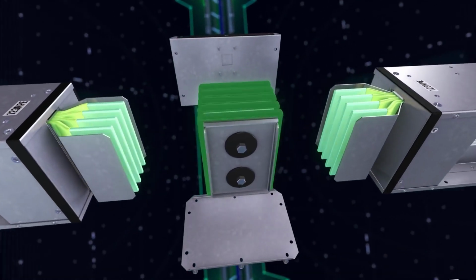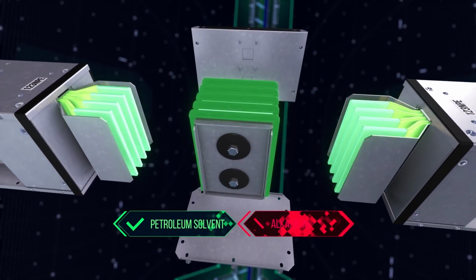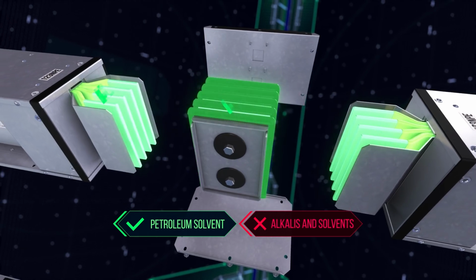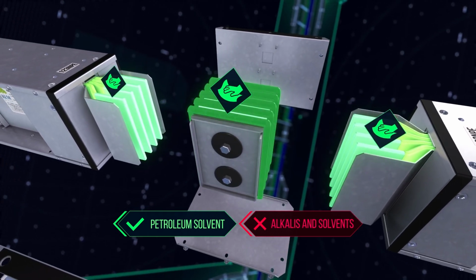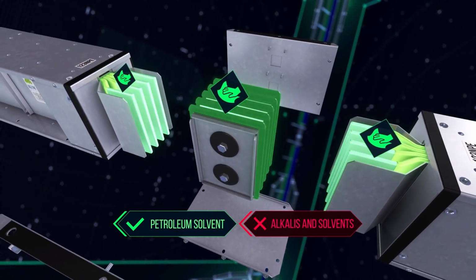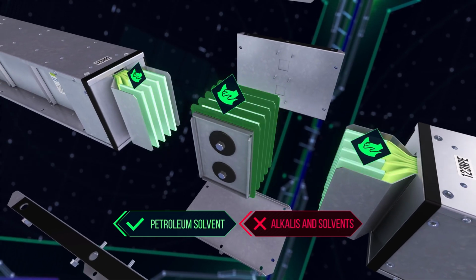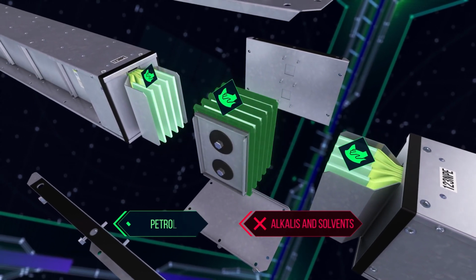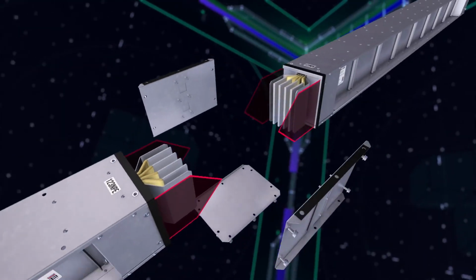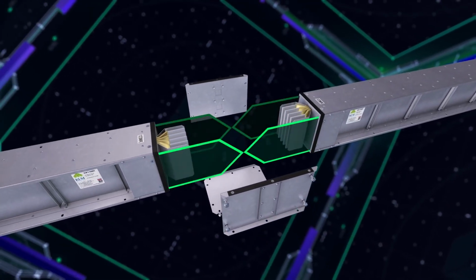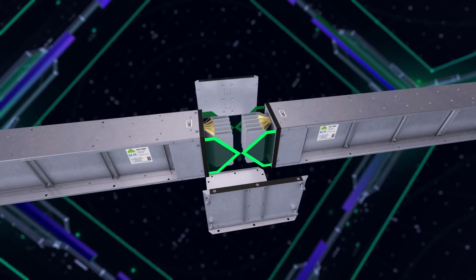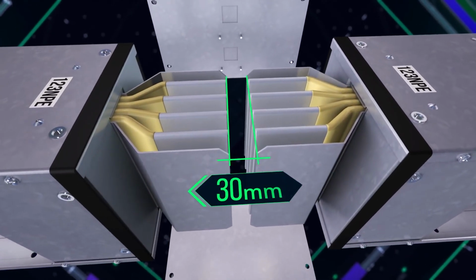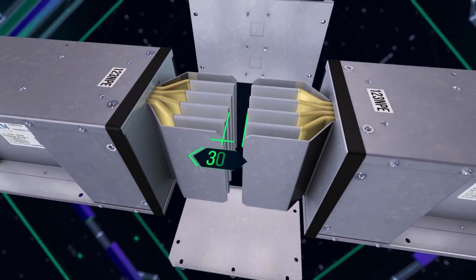Carefully inspect the current conducting parts of the busbar trunking system sections and junction units. Clean them using a soft cloth and petroleum solvent or similar. Compounds containing alkalis and other solvents should not be used. When installing sections of the busbar trunking system, make sure that the junction units are aligned. Position the ends of the current conducting buses 30 mm apart from each other.